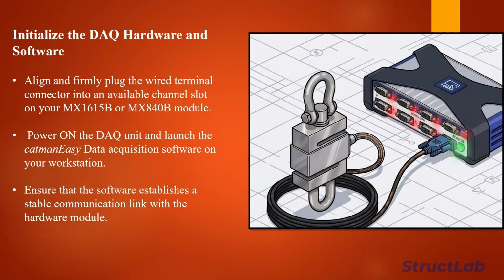Step 6. Initialize the DAQ hardware and catmanEasy software. Align and firmly plug the wired terminal connector into an available channel slot on your MX 1615B or MX 840B module. Power on the DAQ unit and launch the catmanEasy data acquisition software on your workstation. Ensure that the software establishes a stable communication link with the hardware module.